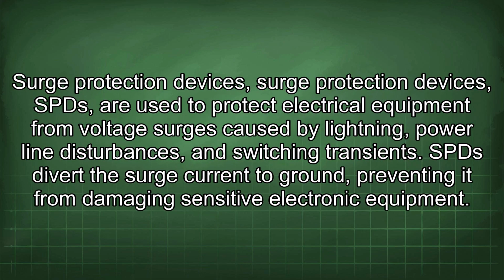Surge protection devices, SPDs, are used to protect electrical equipment from voltage surges caused by lightning, power line disturbances, and switching transients. SPDs divert the surge current to ground, preventing it from damaging sensitive electronic equipment.